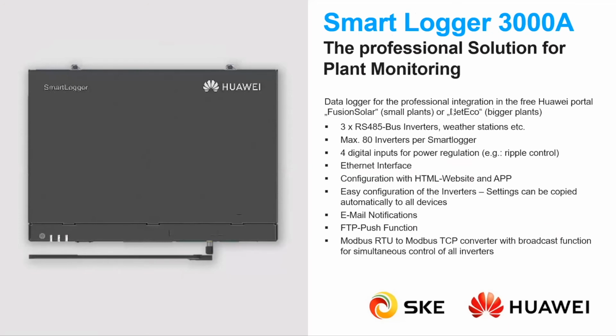For more complex configurations, when you have more than 10 inverters, you can use this device, which is called the smart logger. And it has a lot of really nice features. Its main purpose is to make the connection between the inverters and the monitoring platform. So you can create a PV plant and monitor everything through this smart logger. I recommend using the smart logger when you have more than 10 inverters in a PV plant. It can handle a maximum of 80 inverters, and it has three communication ports where you can add these inverters. Per each communication port, you can have 30 inverters. And for all three of them, you can have a maximum of 80.